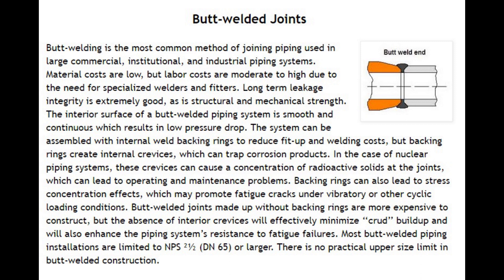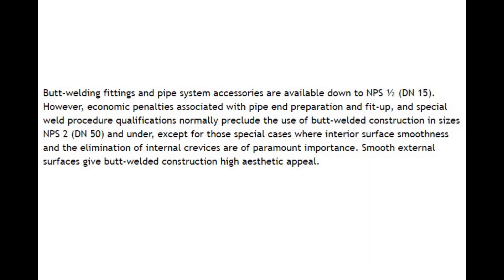Most butt welded piping installations are limited to NPS 2½ (DN65) or larger. There is no practical upper size limit in butt welded construction. Butt welding fittings and pipe system accessories are available down to NPS ½ (DN15). However, economic penalties associated with pipe end preparation and fit-up, and special weld procedure qualifications, normally preclude the use of butt welded construction in sizes NPS 2 (DN50) and under, except for special cases where interior surface smoothness and the elimination of internal crevices are of paramount importance.